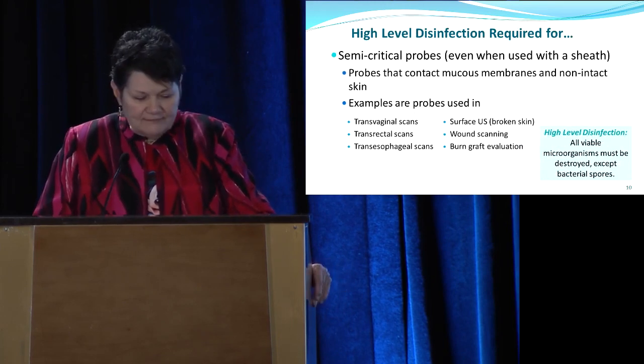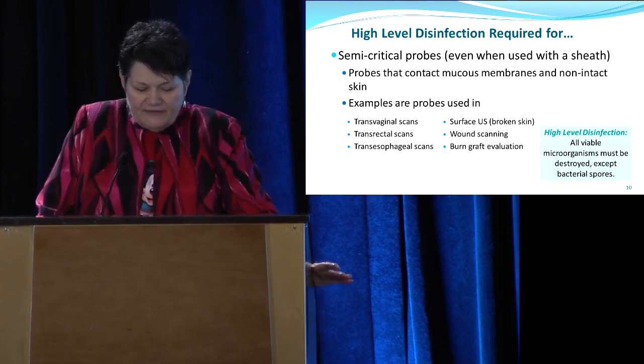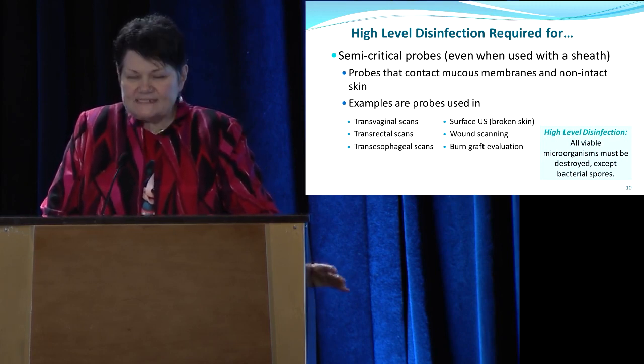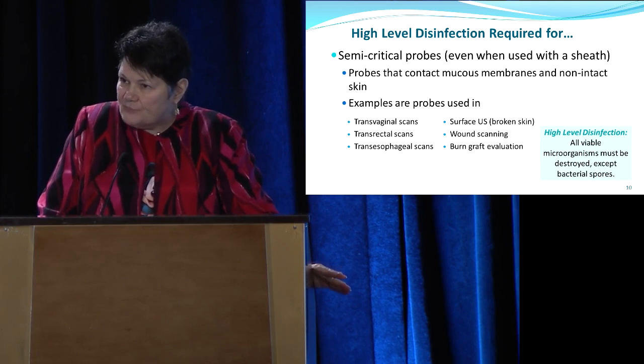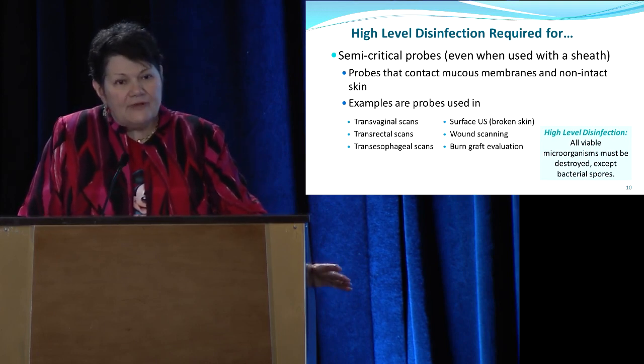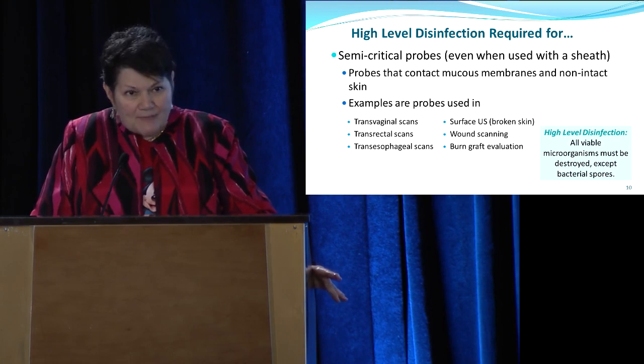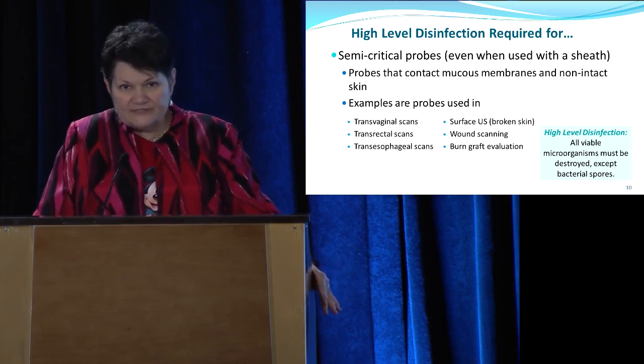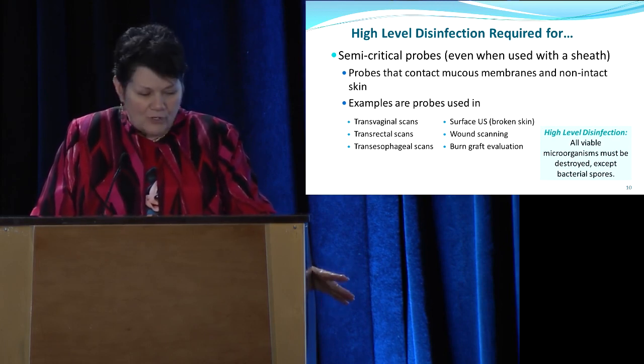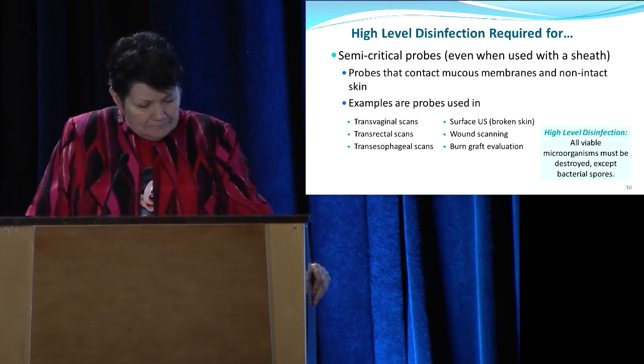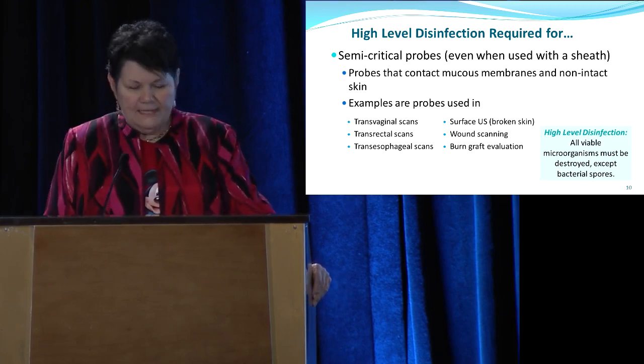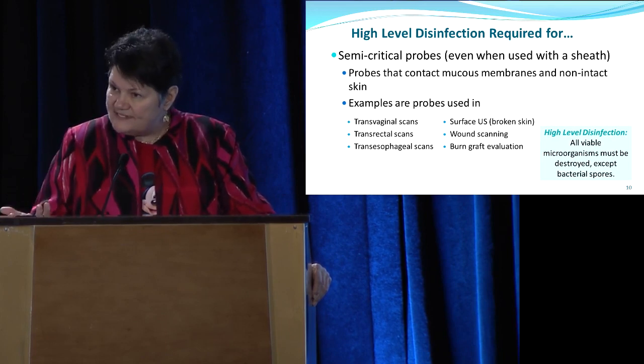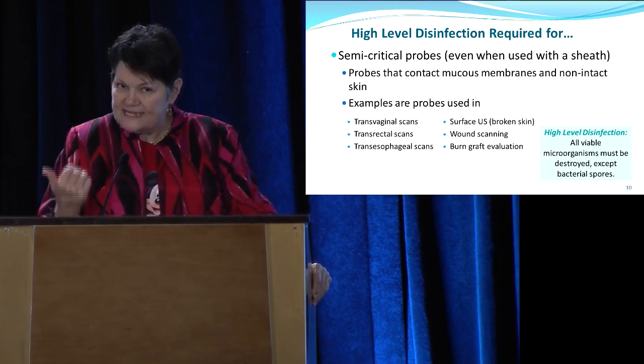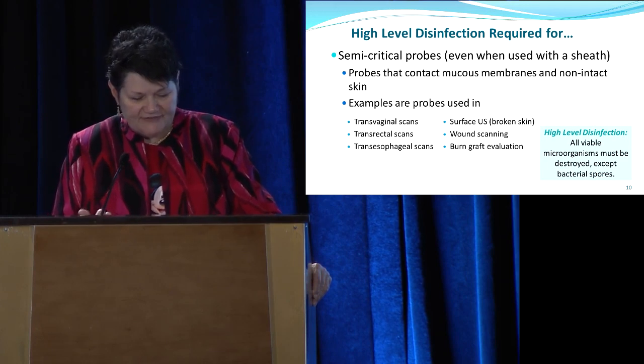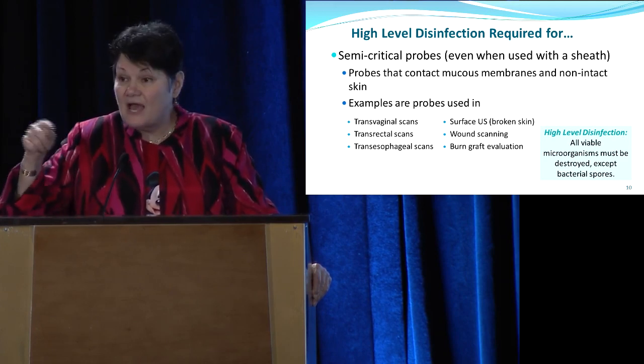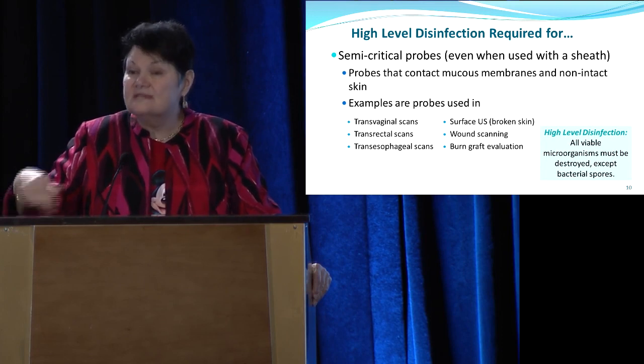High-level disinfection, which is the killing of all viable microorganisms except for large numbers of bacterial spores, is required for anything that's going to touch mucous membranes. So again, anal and rectal probes, vaginal ultrasound probes, TE probes, that kind of thing. If you've got broken skin, it goes into that category, because it's only for intact skin that you can use a low-level disinfectant.